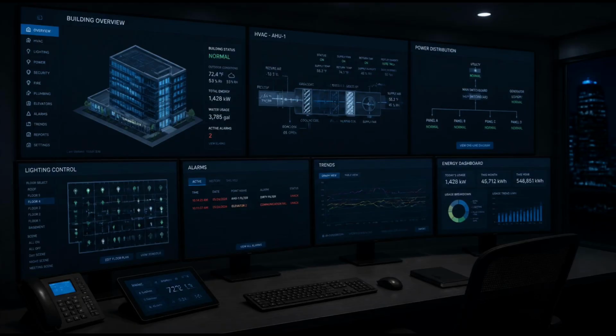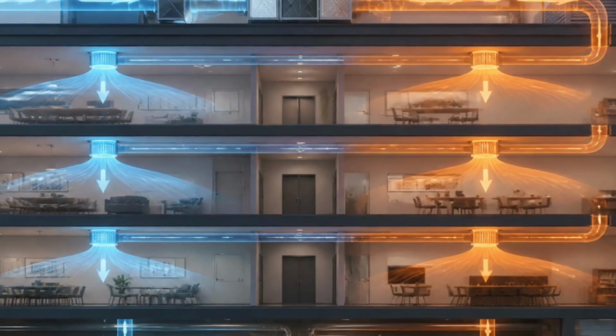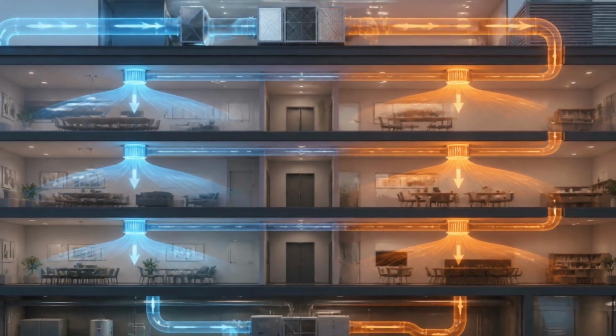The set point temperatures are also adjusted. Instead of maintaining a precise 72 degrees for occupant comfort, the building may be allowed to drift to 76 or 77 degrees on a warm night or down to 68 degrees on a cool one. This expanded temperature range requires less mechanical effort to maintain and allows the system to run with less energy during the hours when no one is present to notice the difference. Low airflow at night can help the building rest while staying protected.